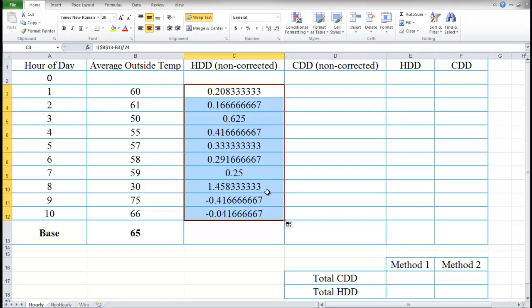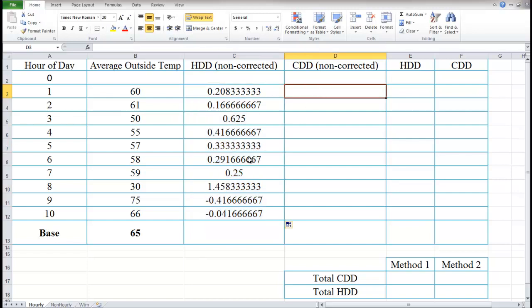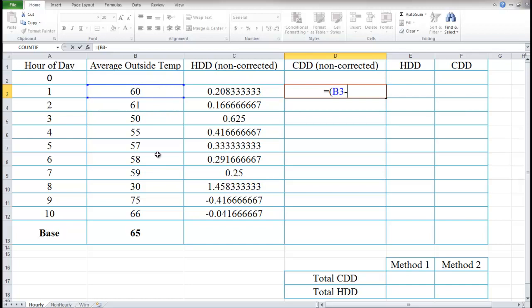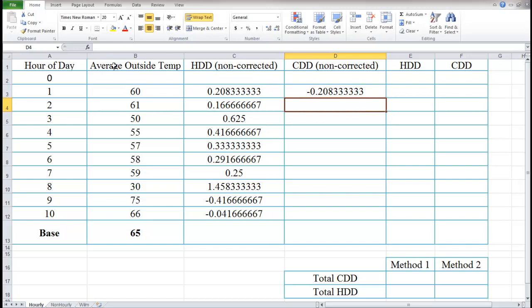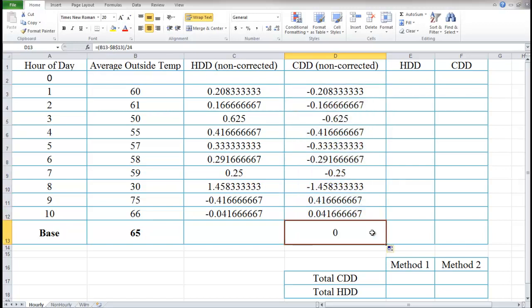Now that's our heating degree days — but it's non-corrected, because heating degree days are not supposed to be negative. That's why I've labeled it 'non-corrected.' Now let's do cooling degree days. It's the same formula except we do the average outside ambient temperature minus the base, divided by 24. This time I'll use F4 right away. Now we can see we have a lot of negative cooling degree days and some negative heating degree days.